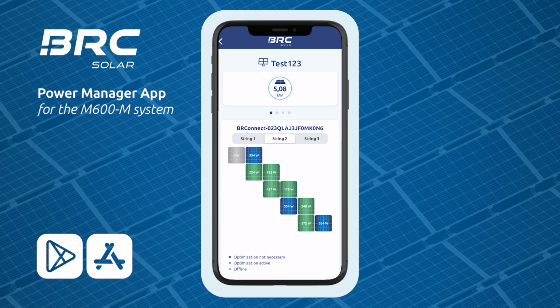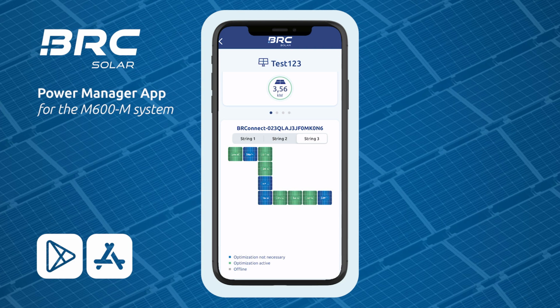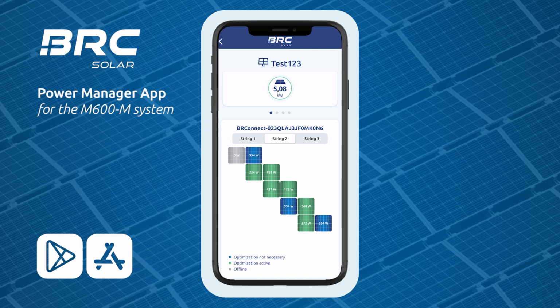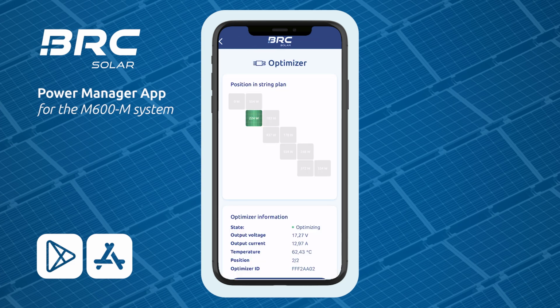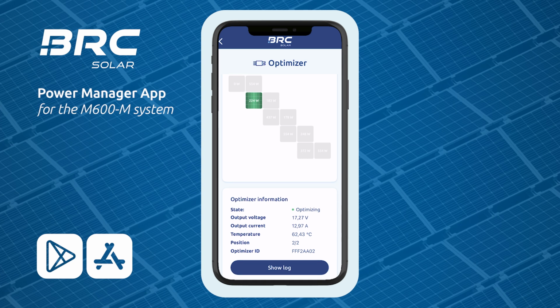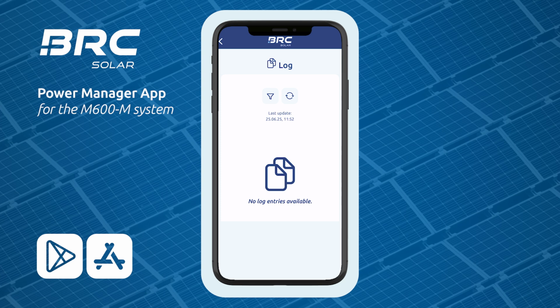You would also see if an optimizer is offline. In this situation, the optimizer would be shown as a gray optimizer. If you want to have detailed information about the module or the optimizer by itself, you can simply click on one of the optimizers and then you get the information of the voltage, the current and the temperature of this one optimizer in the string. With show log, you would also get all the information and messages of the optimizer. So if there was a problem in the past and stuff like that.